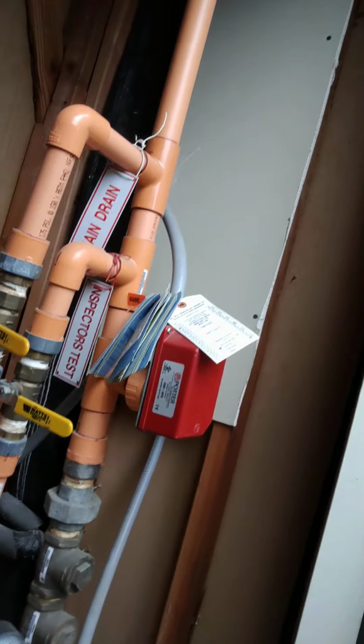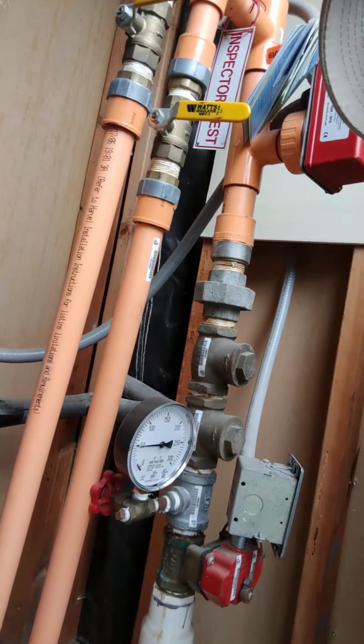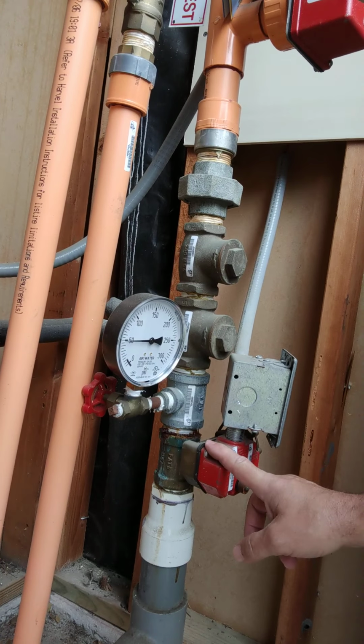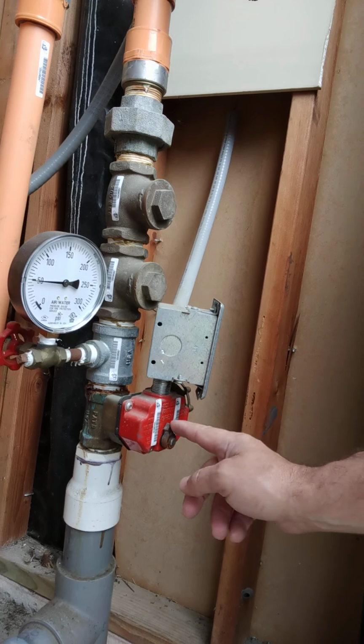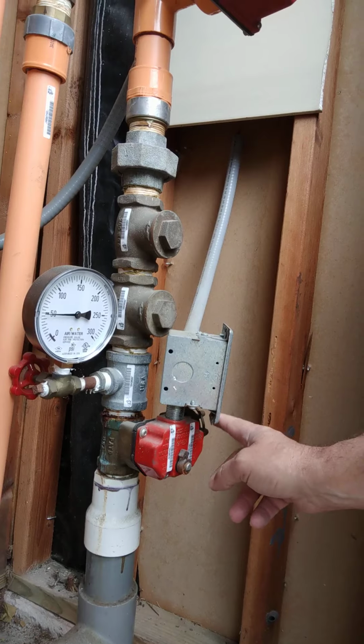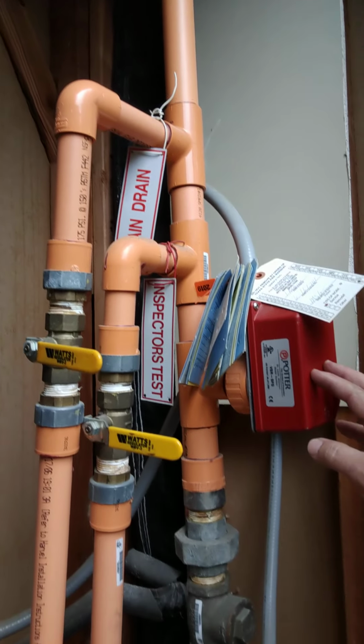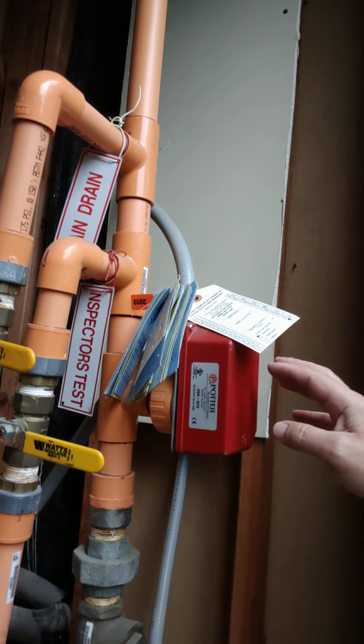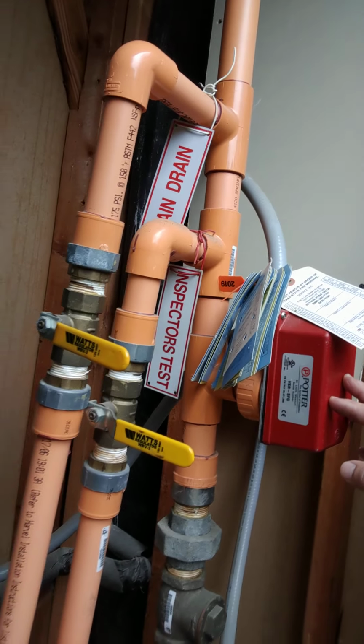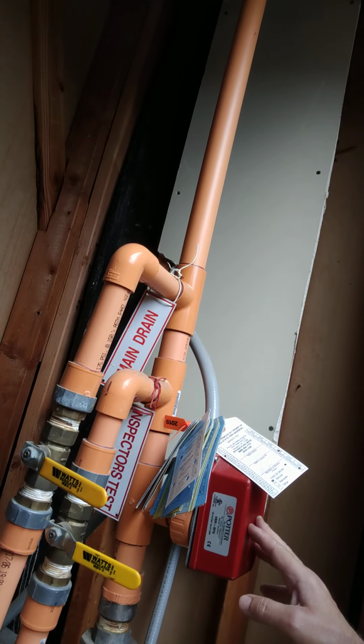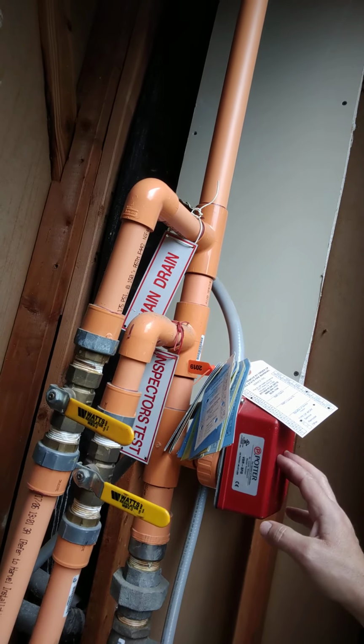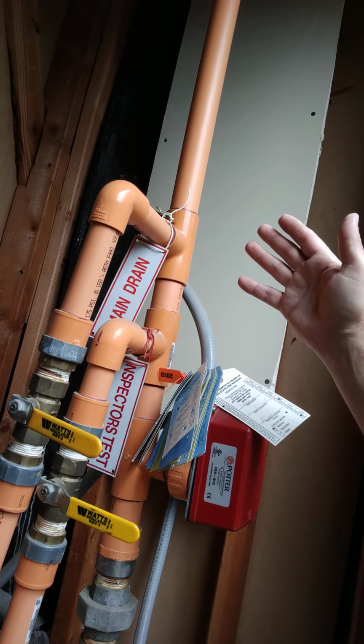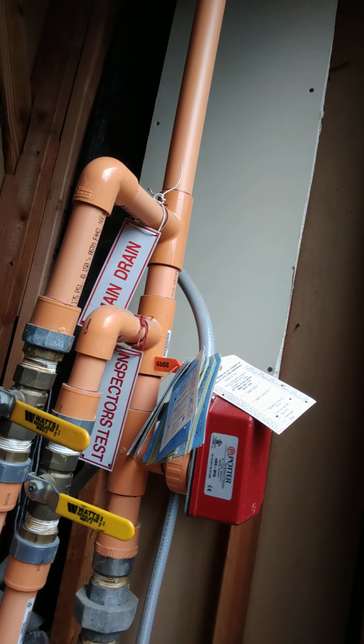Let's take a look at a couple of things. On the sprinkler riser, you're going to see that we've got this red box here. It's got a valve here, an indicator that tells you open or shut. And we've got another sensor right here. These are flow sensors, okay? So if ever a sprinkler head goes off, these are going to detect the water flow through the pipe, and it's going to set off the alarm.